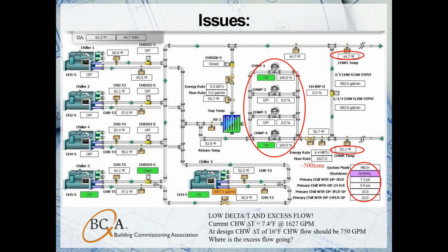So they basically have 4 800-ton chillers that can operate independently. However, they're not able to operate at part load as well, and the load just isn't there. At lower temperatures, and we're not talking about that low, we're talking about under 60 degrees, they're ending up false loading their chiller plant.